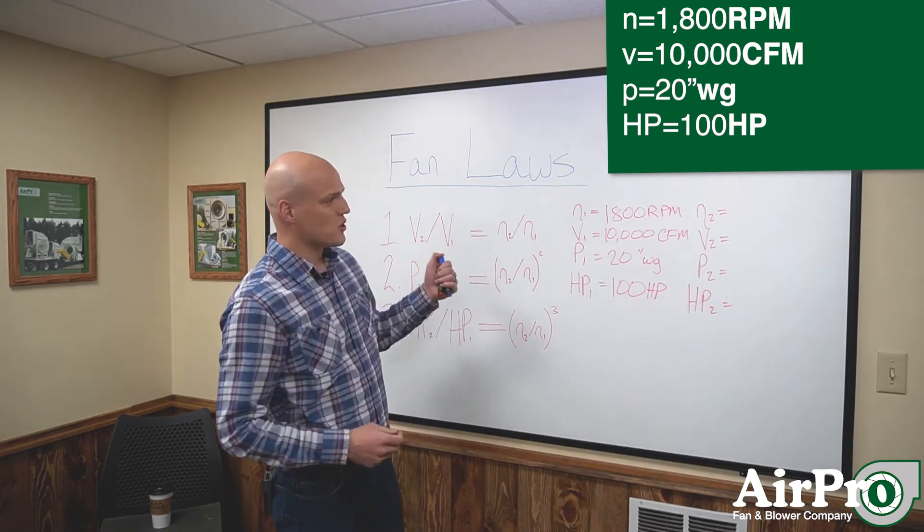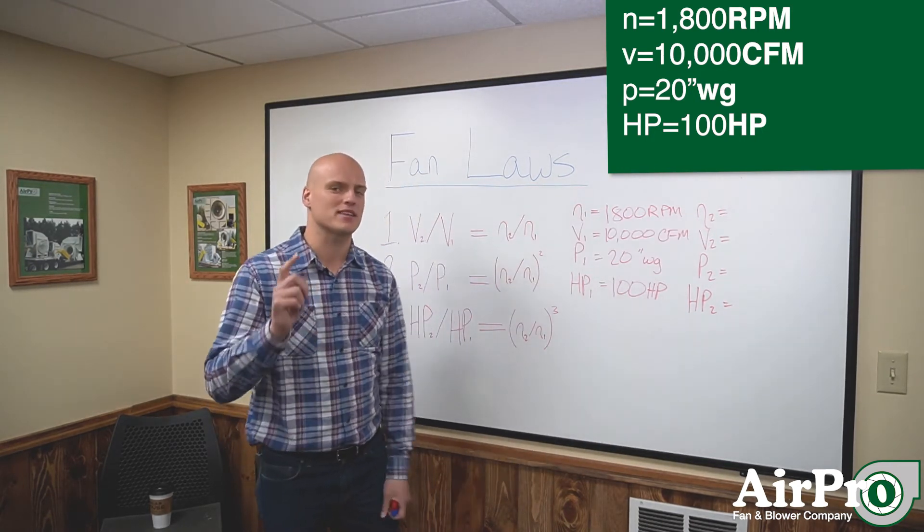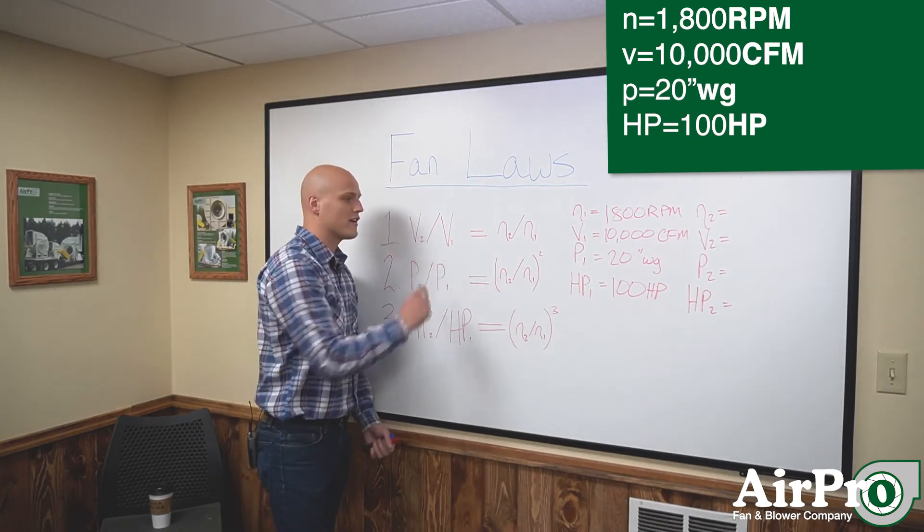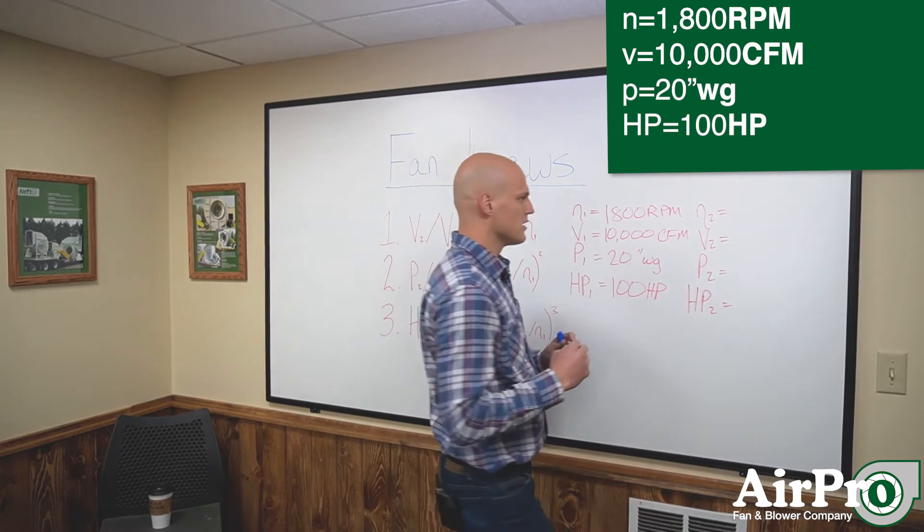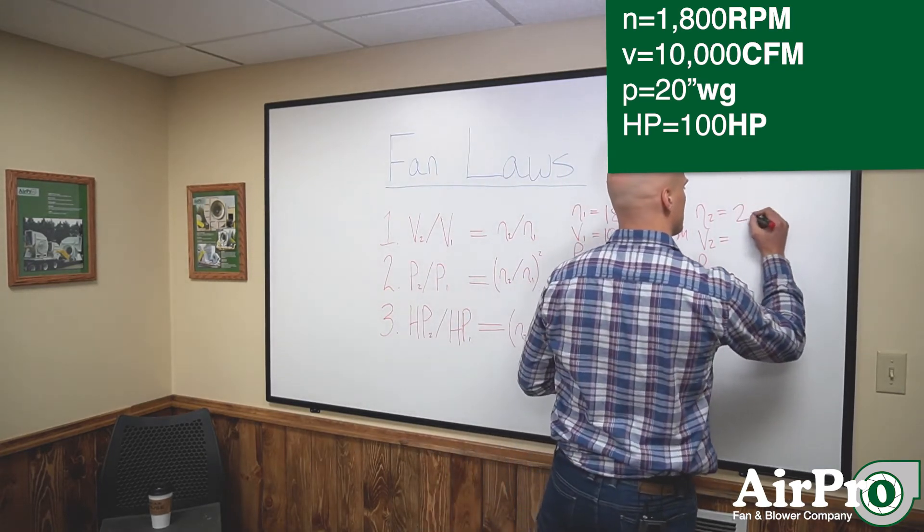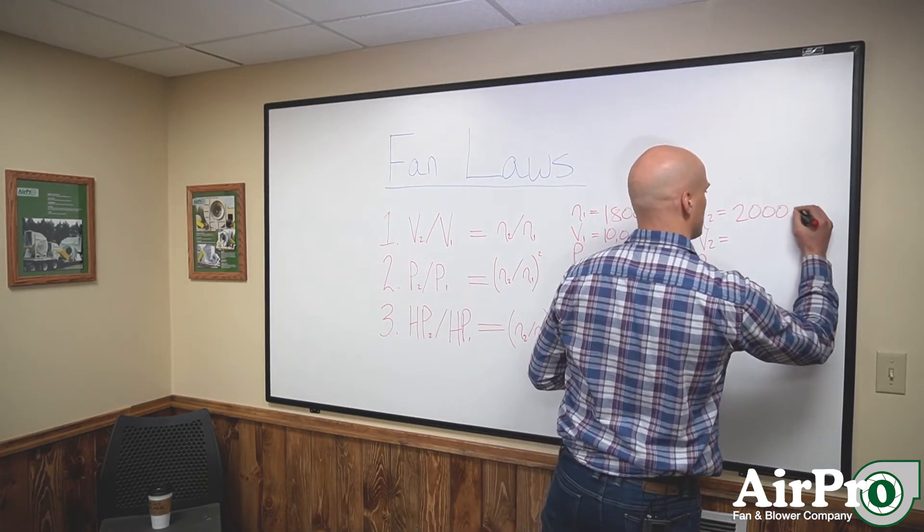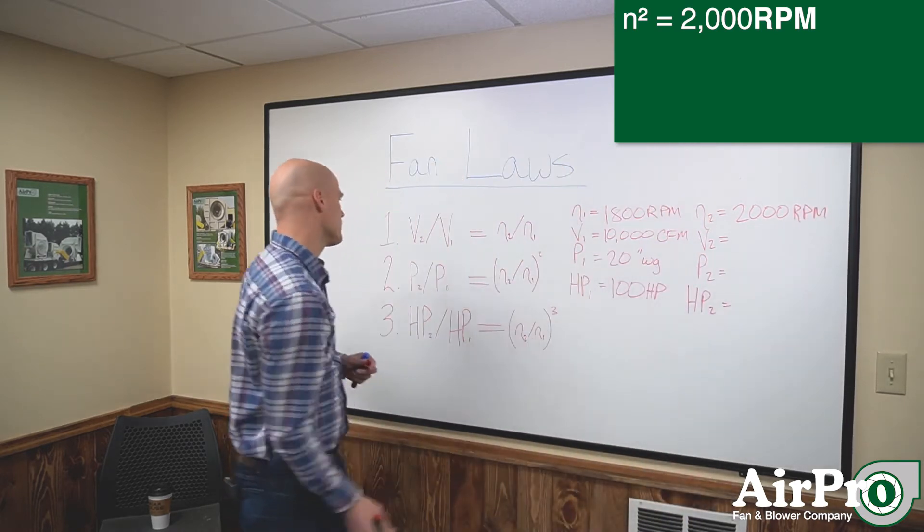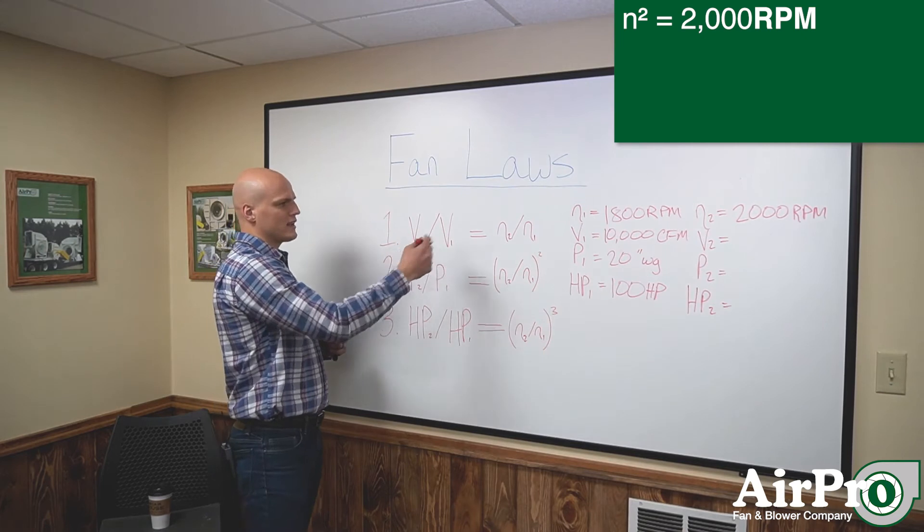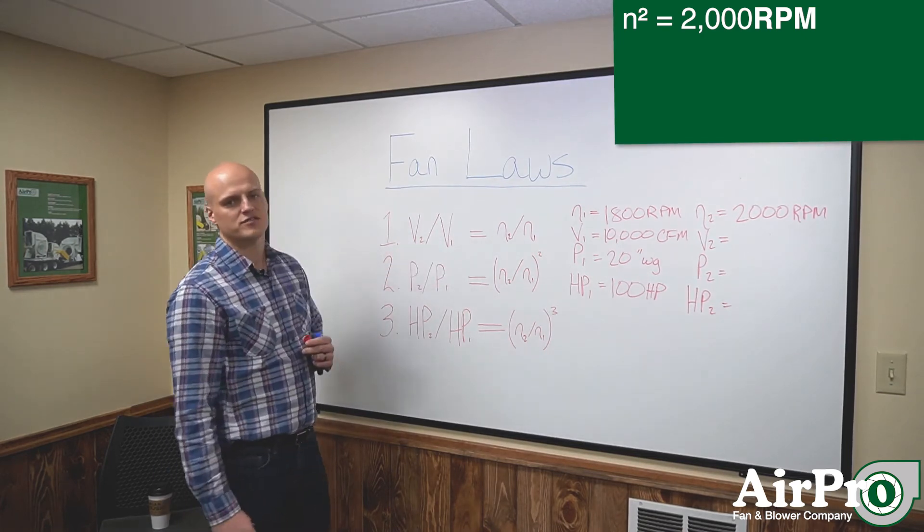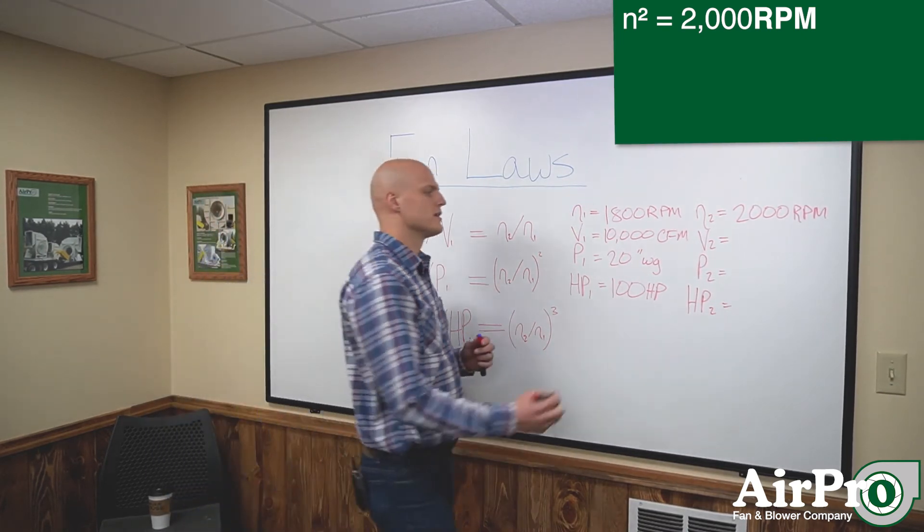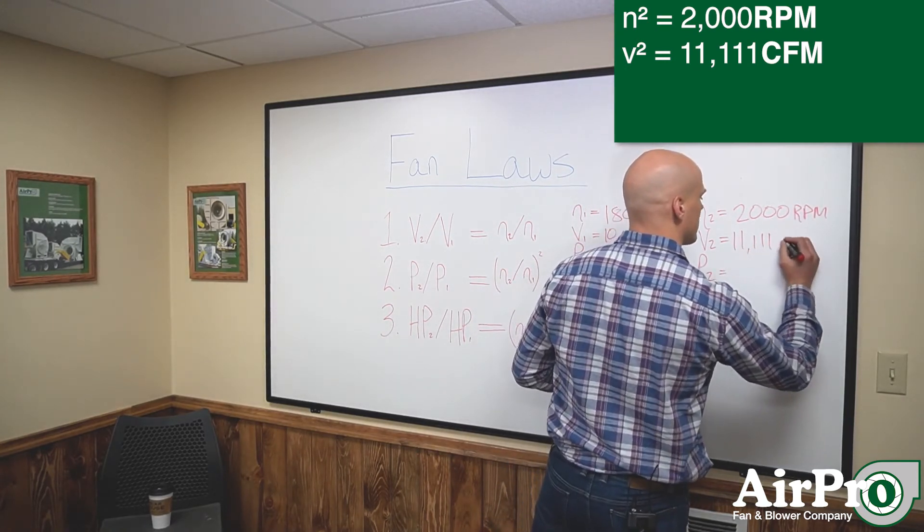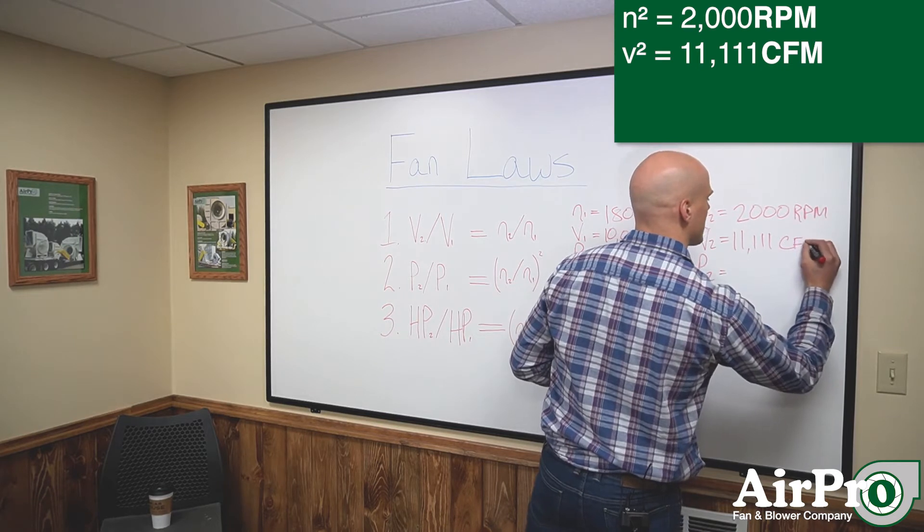We're going to show you what happens if you take your speed up to 2,000 RPM using fan laws. So what happens when we speed the fan up? Volume, we're going to gain a factor of 2,000 to 1,800. That is 11,111 CFM.